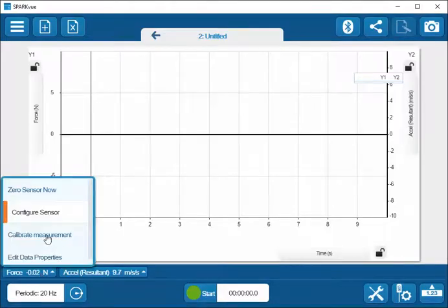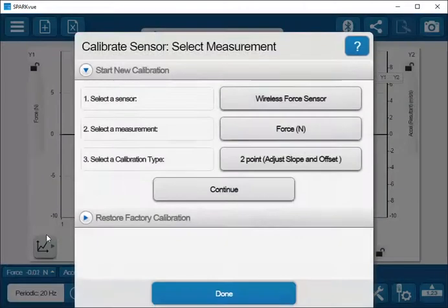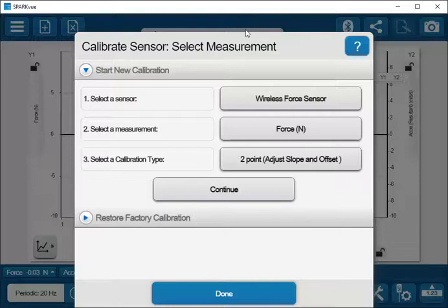The third option is I can go through the calibration of the sensor. This is possible for any sensor that it is possible to calibrate. I can click on this, and then I'm presented with the Calibrate Sensor menu, and I can proceed with the calibration of this sensor.